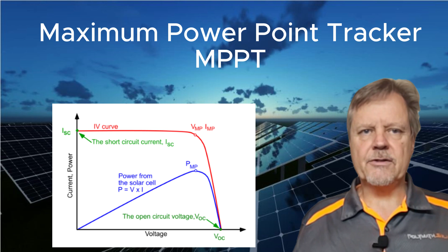Here's the catch with the MPPT. All the panels connected to an MPPT, whether it's 1 or 50, have to have the same orientation, the same slope, the same size panel - they have to be identical, because the MPPT manages all those panels as if they're one panel. So if you have only one MPPT, all the panels have to be on one face of your roof. If your house has two different sections, one facing east and the other facing west, you must have two MPPTs - one to manage the eastern panels and one to manage the western panels.